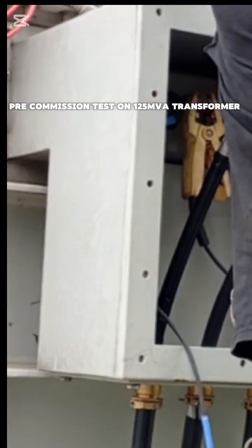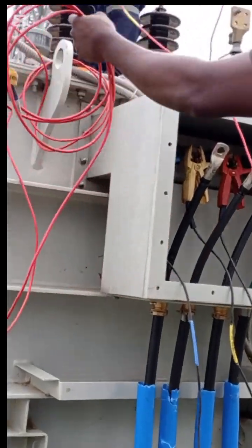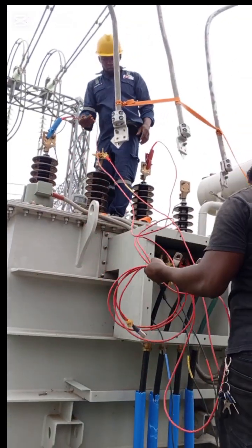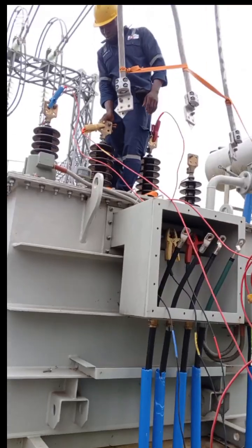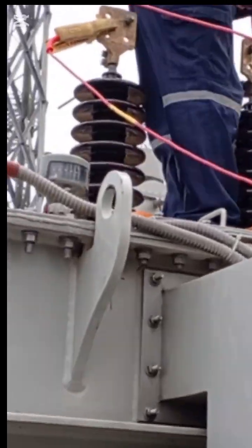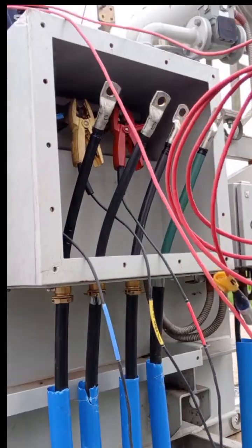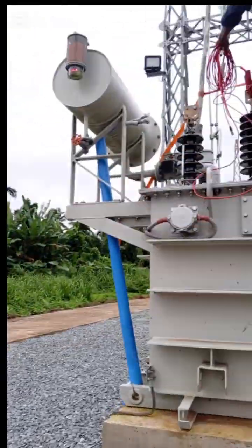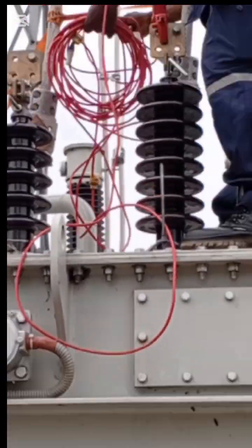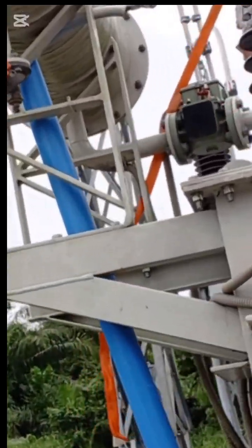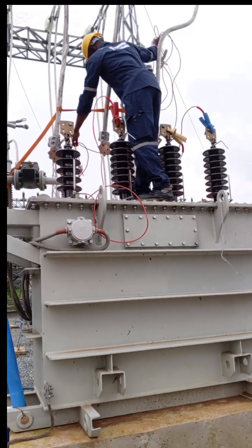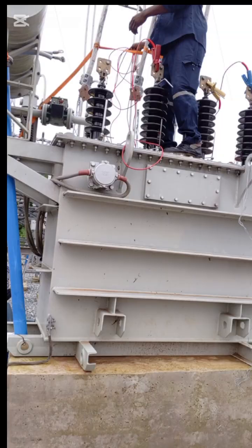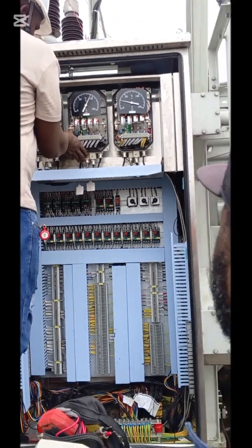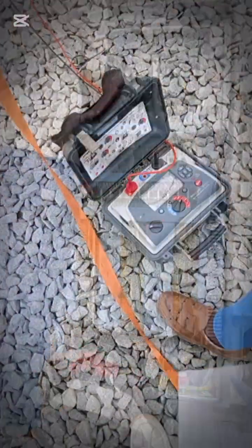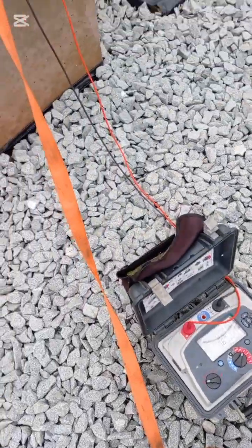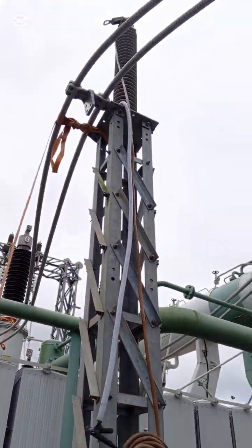Important tests necessary before commissioning a transformer. You're looking for the most important and necessary tests for a transformer before it's put into service, following industry standards. For a 125 MVA transformer, this is a critical process to ensure reliability and safety. While the full list of tests can be extensive, here are the absolutely necessary and most important tests, generally aligned with IEEE C57.12.90 and IEC 60076 series standards, which are the leading guidelines.